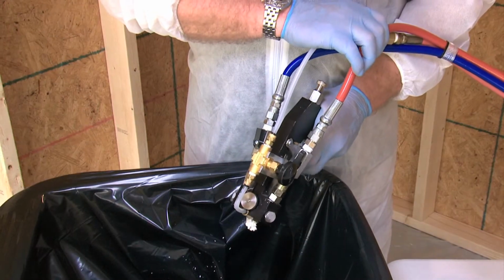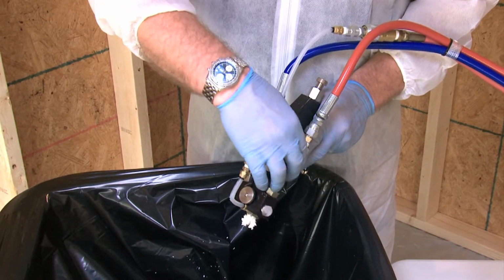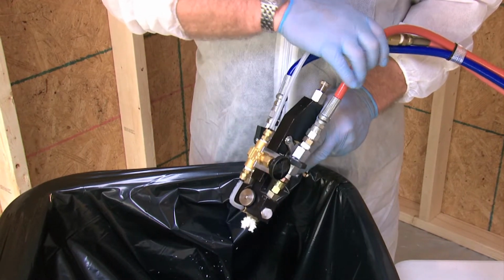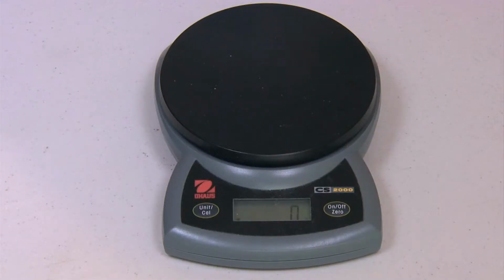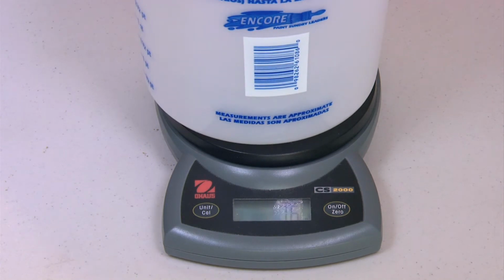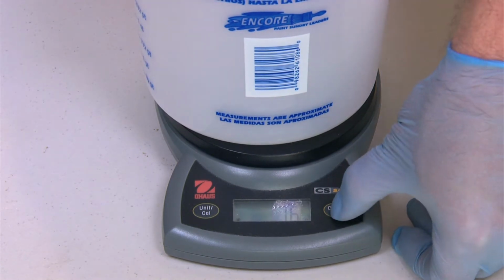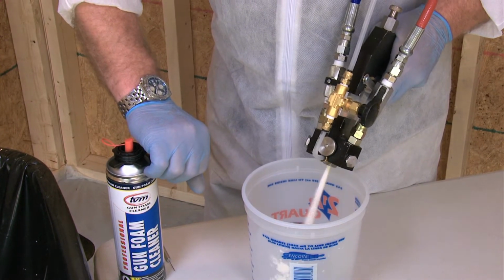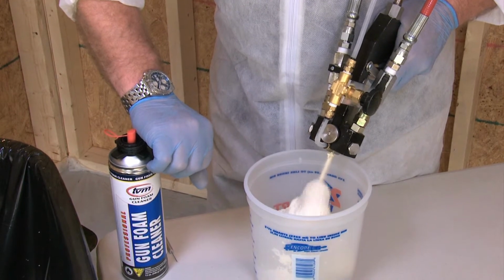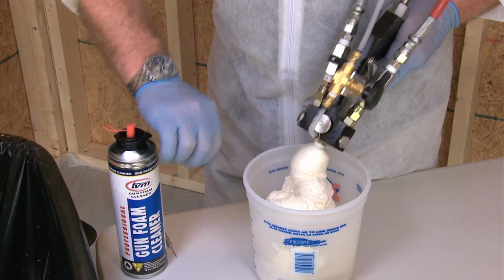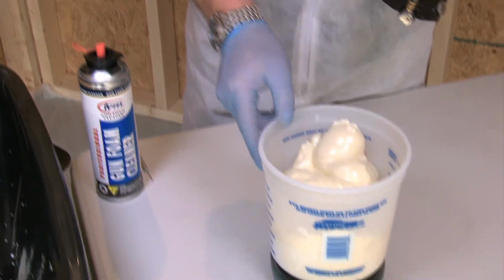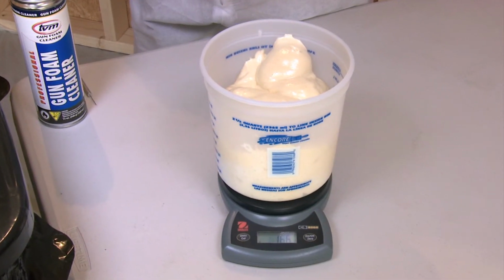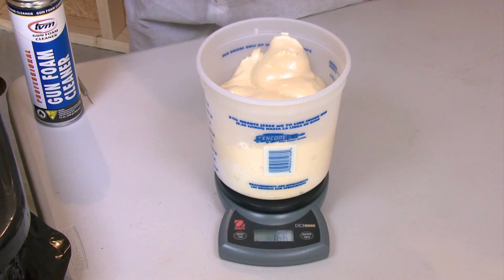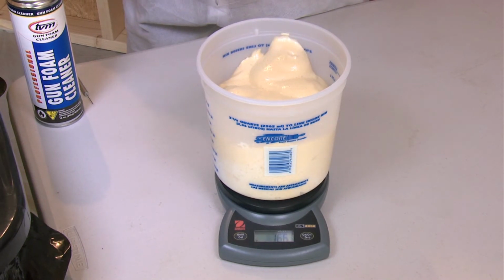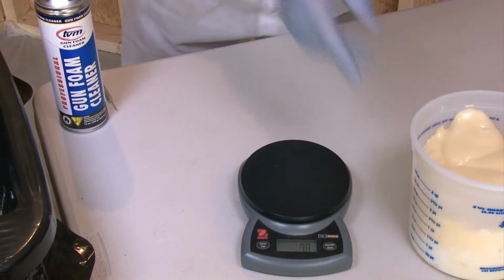Now, close the A chemical valve on the dispenser, leaving the B chemical valve open. Place a new 32-ounce cup on the scale. Tare the scale to read 0 and remove the cup. Using a stopwatch, fully depress the trigger on the dispenser for exactly 3 seconds, directing the flow of the B chemical into the cup. Repeat the critical steps to purge the dispenser. And then place the cup on the scale and record the weight of B chemical dispensed.